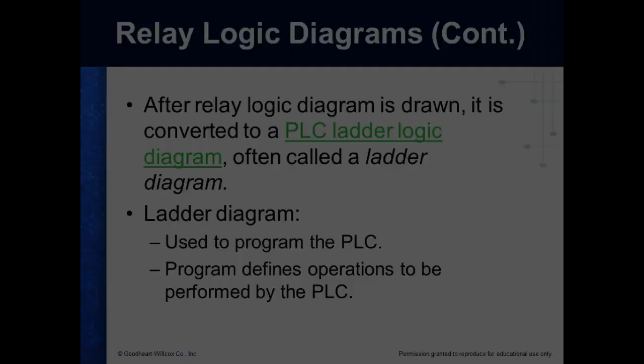There's voltage between the rails, so we call these rails. They are generically labeled L1 and L2. When you get into actual diagrams out in industry, how many L1s and L2s do you think you have? What they usually do is end with L1 or L2, but precede it with some type of letters - they might call it PCL1 and PCL2. This gets very confusing in motor controls because we've got an L1, L2, and L3 that are 208 volts, and then an L1 and L2 that's 120 volts.